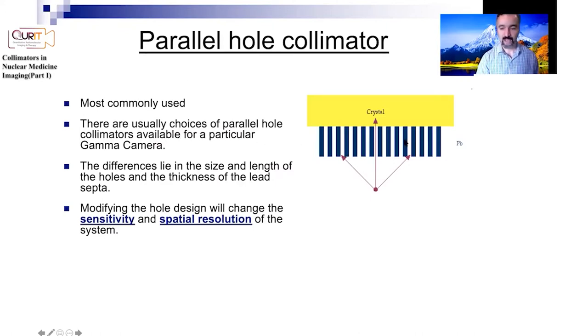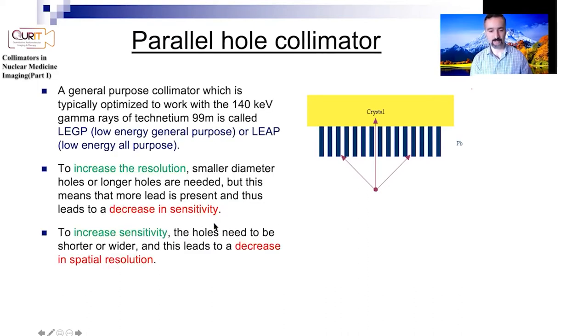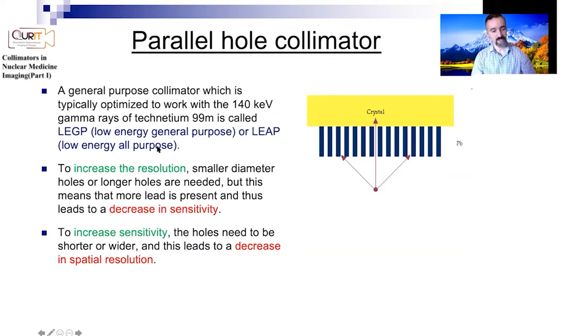How thin, thick, or tall you make the collimator depends on the application. Changing the size of the hole, the thickness of the septa, or the length of the holes all have implications on the sensitivity of the system and its spatial resolution. What is most commonly used is the low energy general purpose collimator — called LEGP or LEAP — designed for 140 keV. For higher energies you need higher energy types of collimators.